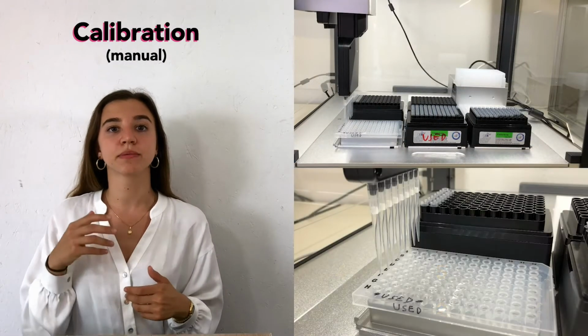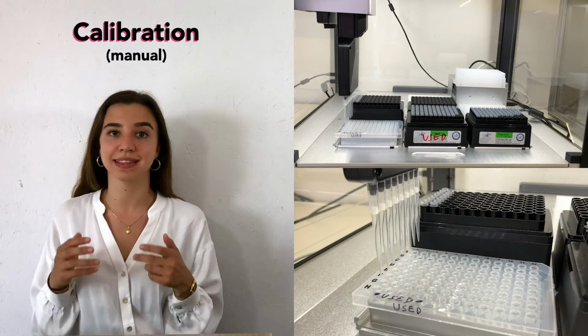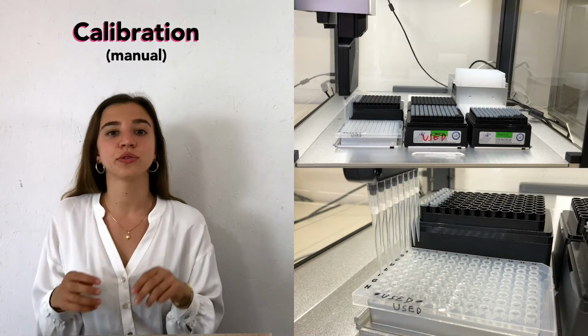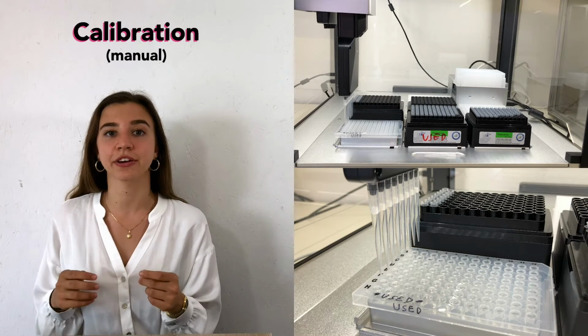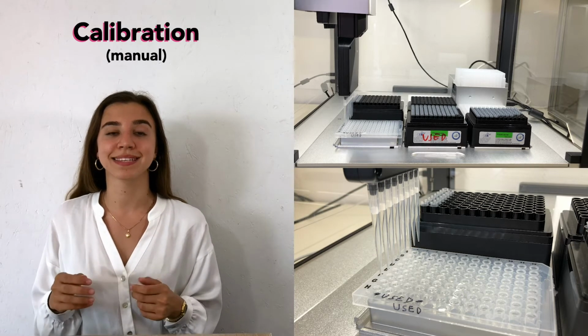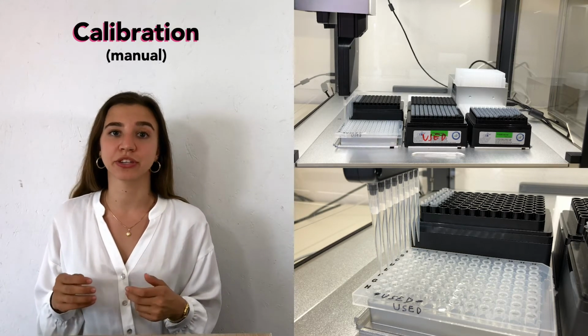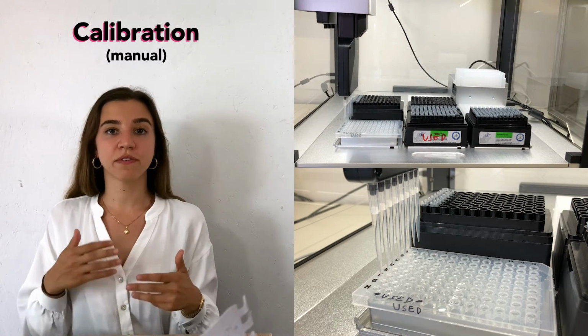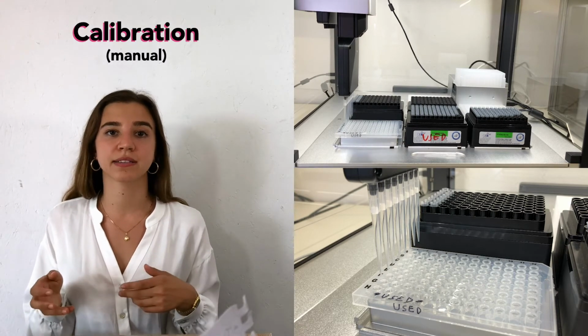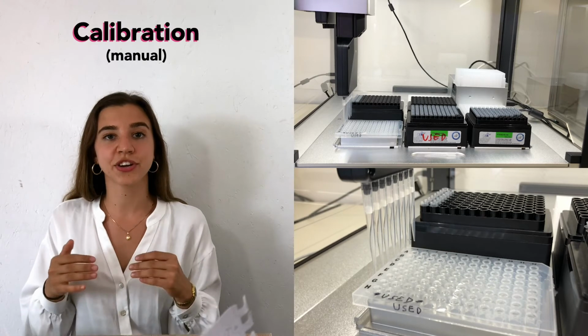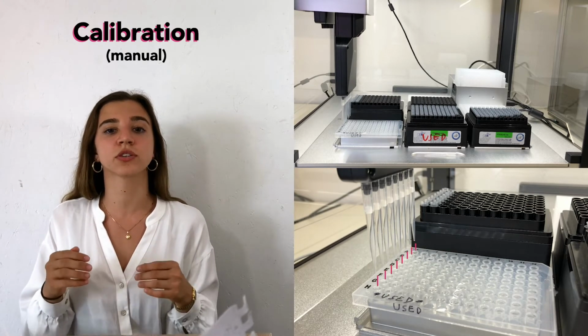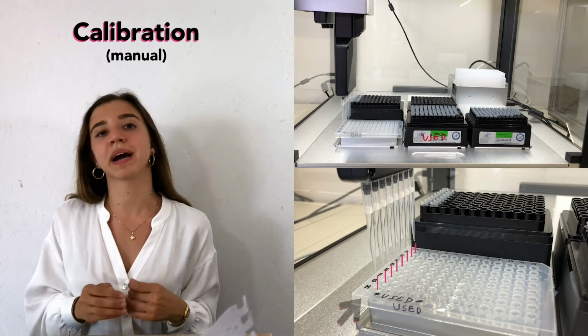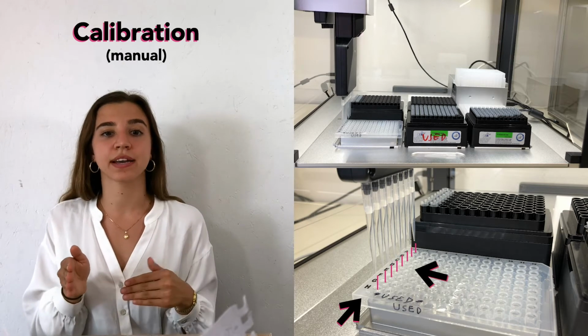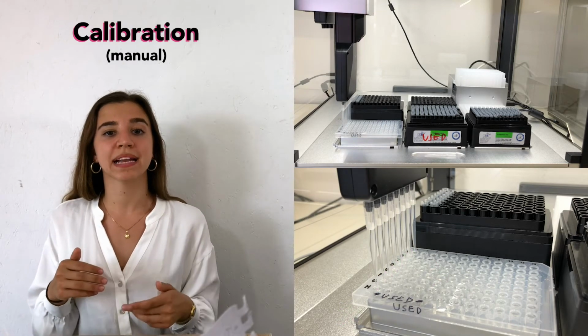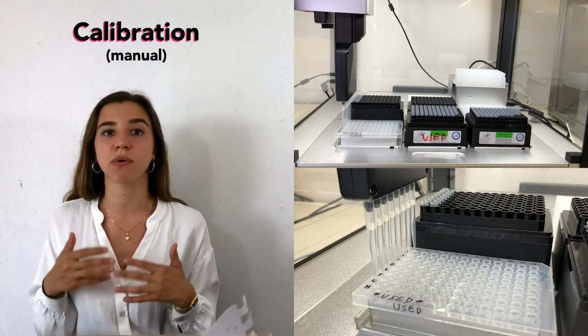The last but most important stage to your calibration is labware. It is essential that you take care to adjust the pipette accurately for each component at this stage, or it could be detrimental to your protocol. This will be very similar to what you did for the tip racks. Ensure that the tips are centered above the wells of the first columns. Double check this by looking head on and to the side. Then lower the pipette tips until they are flush with the top of the wells.